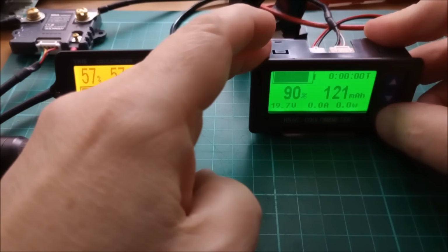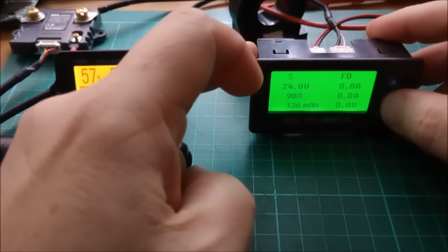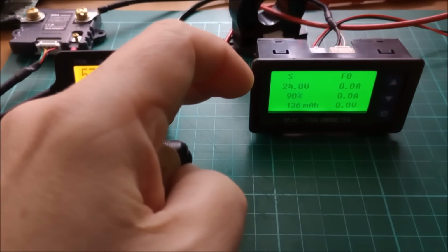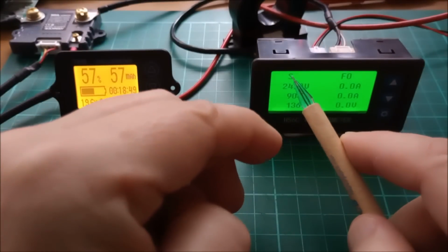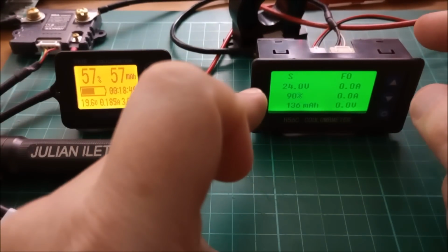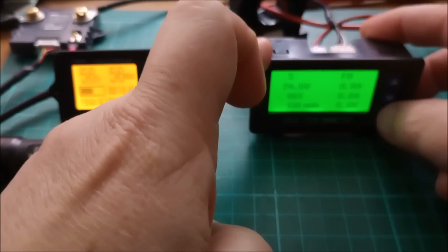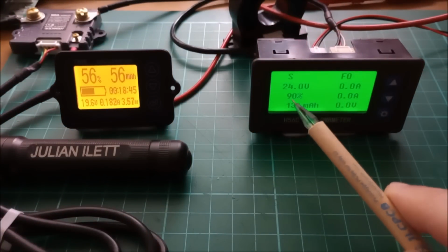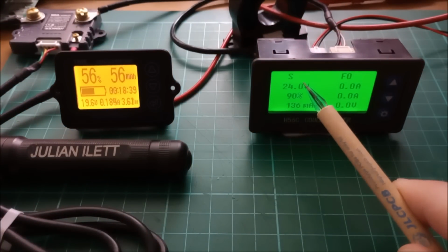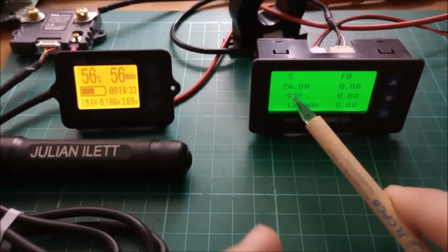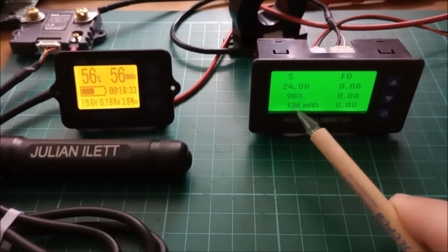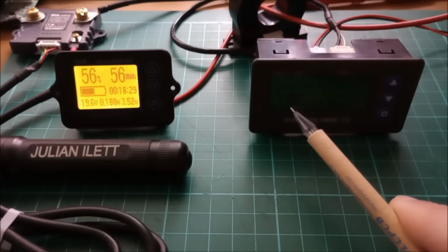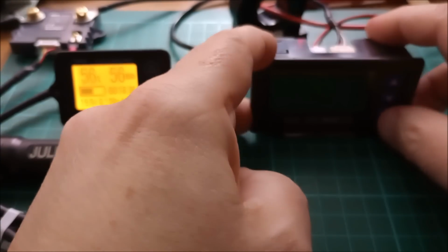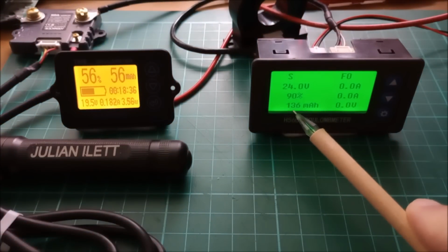If I go into - no, I didn't want to go into the settings for this one, I wanted to go into this sub menu. You can now see that it's in S mode, or set mode, and that's because when it got to 24 volts, I pressed and held the upper button, and this captured the values of 24 volts - that's what it was when I held that button - and 136 milliamp hours.